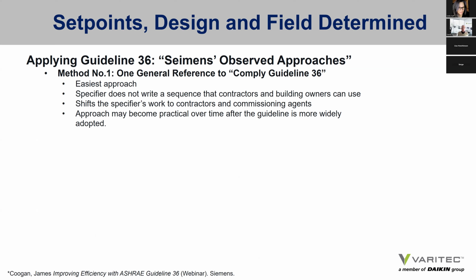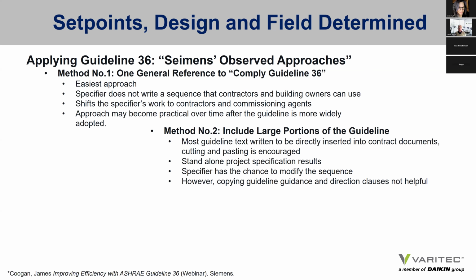It doesn't take them any time, but the specifier does not write a sequence that contractors and building owners can use. The contractors, building owners and commissioning agents have to cipher through all of the guideline to have their own interpretation of what they mean. So that could add confusion during startup and commissioning. However, the approach may become practical in the years ahead as the guideline is more widely adopted, and there'll be a common understanding of what the sequences are when Guideline 36 is referenced in relation to a VAV system, a chilled beam system, etc.